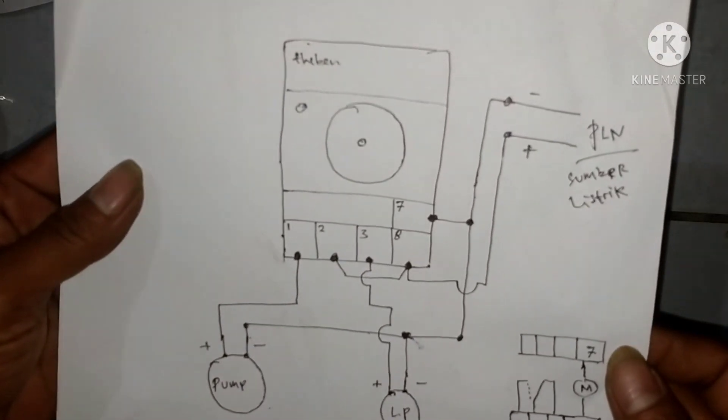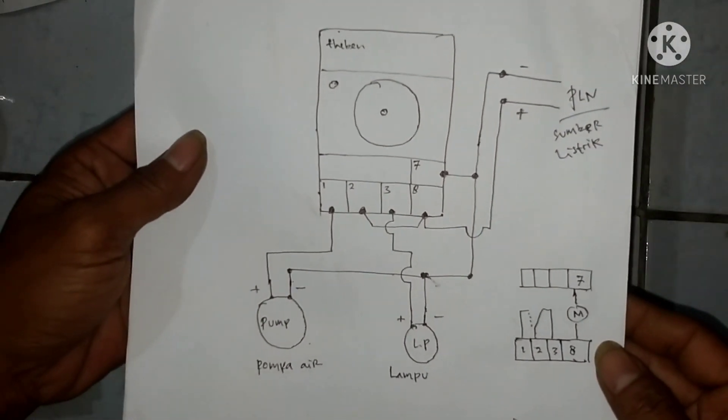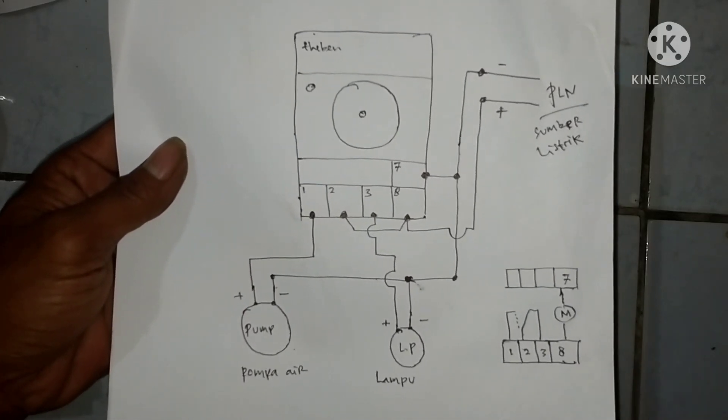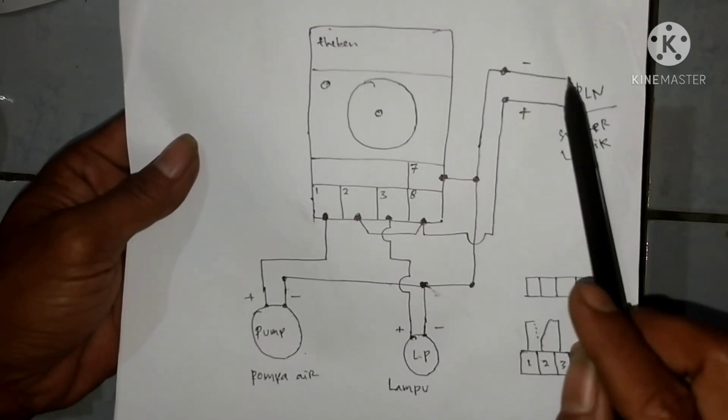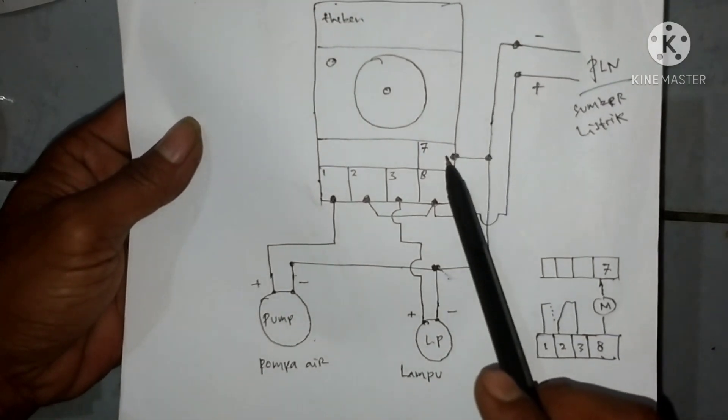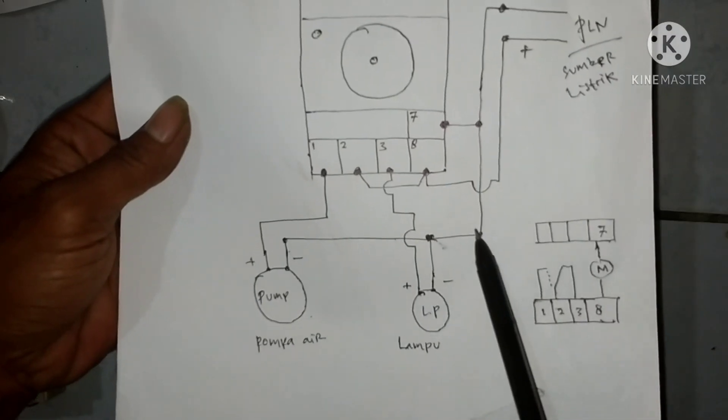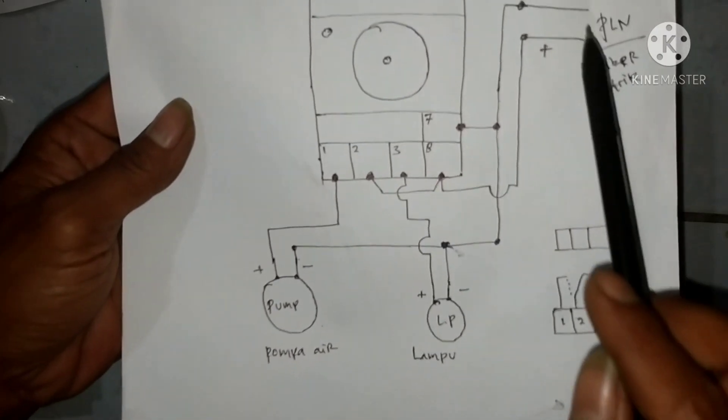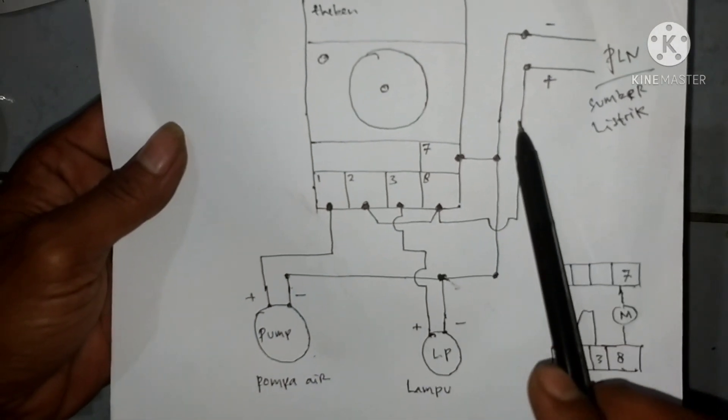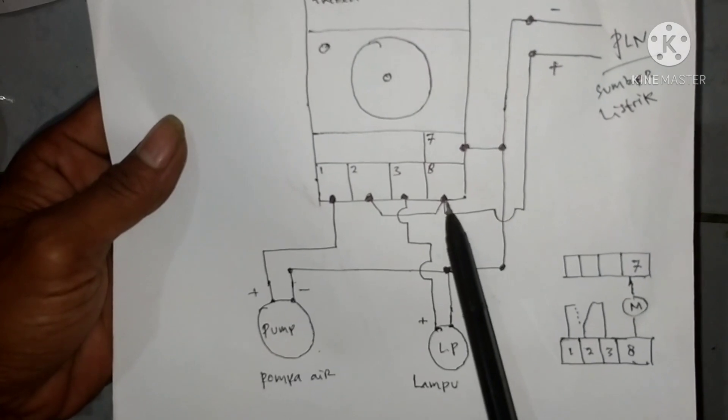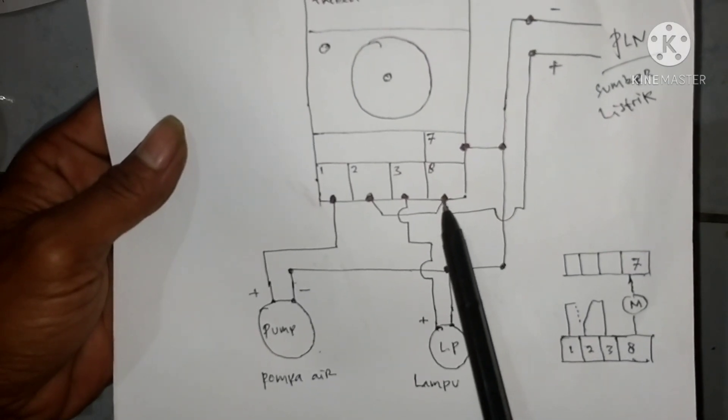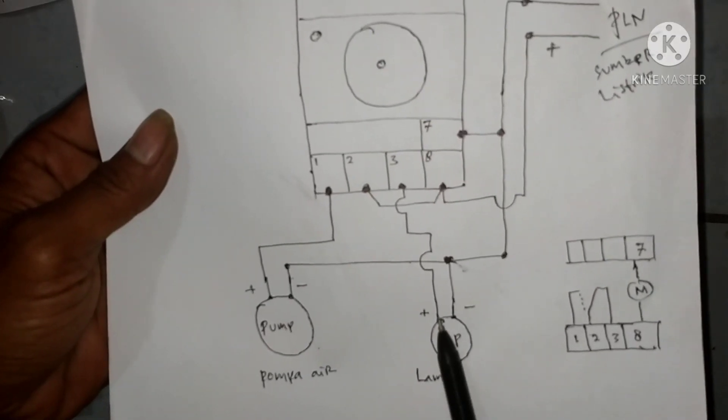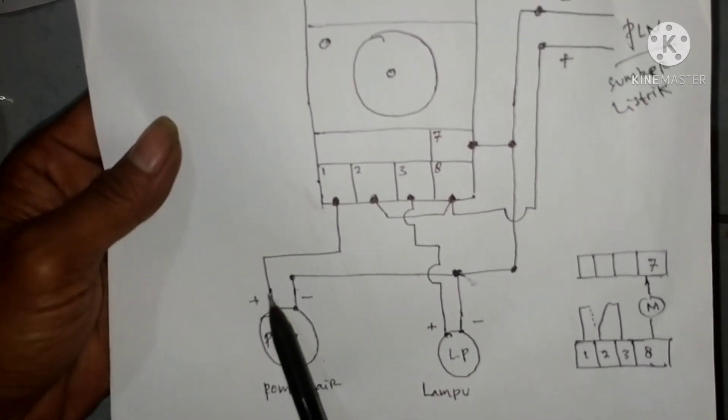Nih teman-teman cukup jelas ya alur-alurnya. Netral ini langsung masuk ke 7 kemudian bypass ke beban, semua beban sama, 1 netral 1 tarikan. Kemudian yang listriknya masuk ke 8 di-jumper ke 2. Nah bebannya masuk ke 3 atau 1.